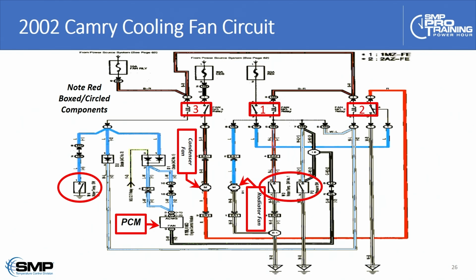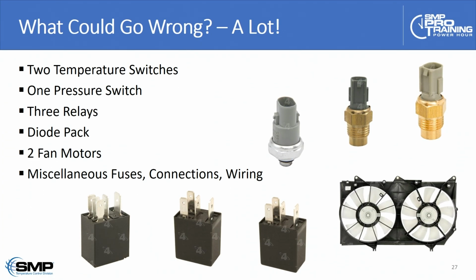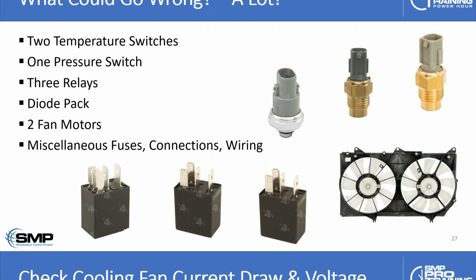So you can imagine if you have a cooling system issue, an overheating issue, an air conditioning performance issue, you might have to sit down with the wiring schematic to understand exactly how these fans work and satisfy yourself that all the pressure and temperature thresholds are being met for all these different switches. So just looking at that one circuit alone, there's, I think, 2 temperature switches, a pressure switch, and there's 3 different relays that are necessary to get those fans to run at all the appropriate speeds.